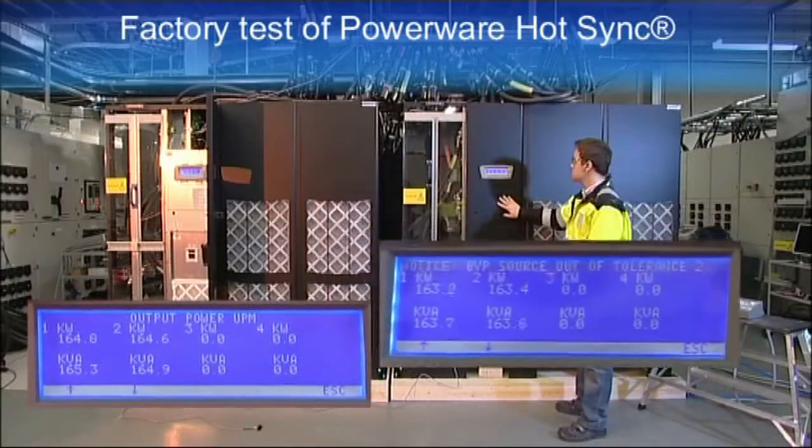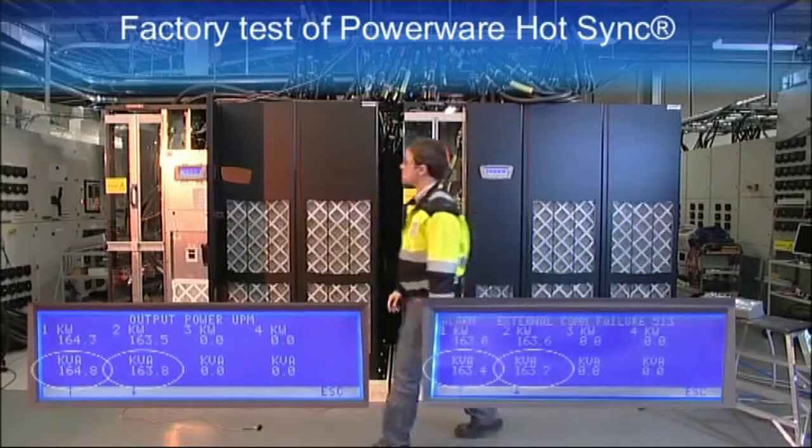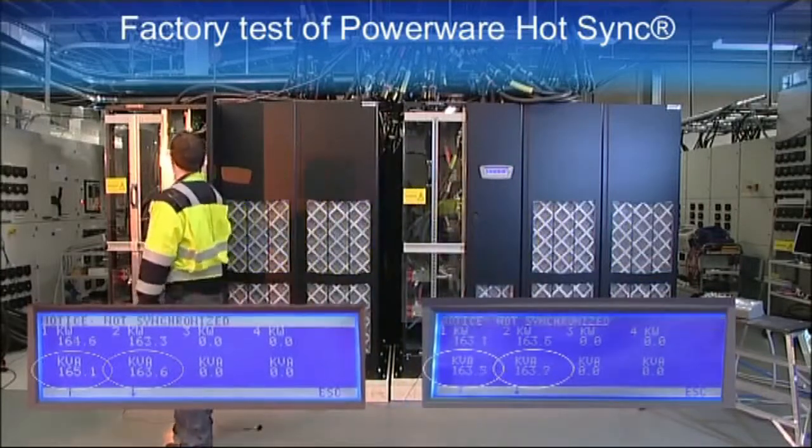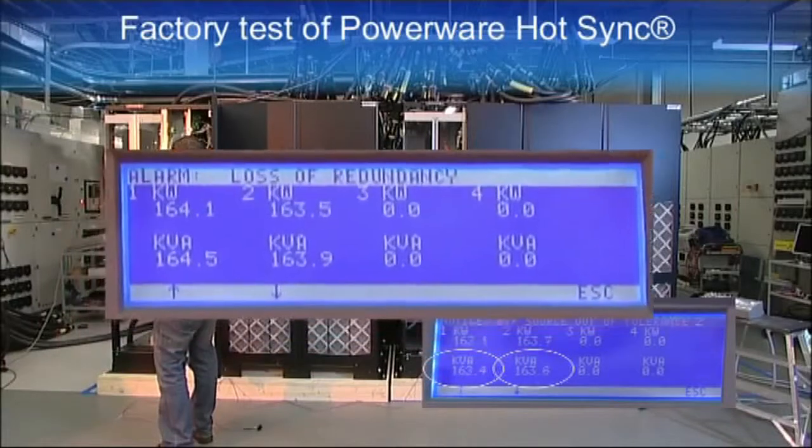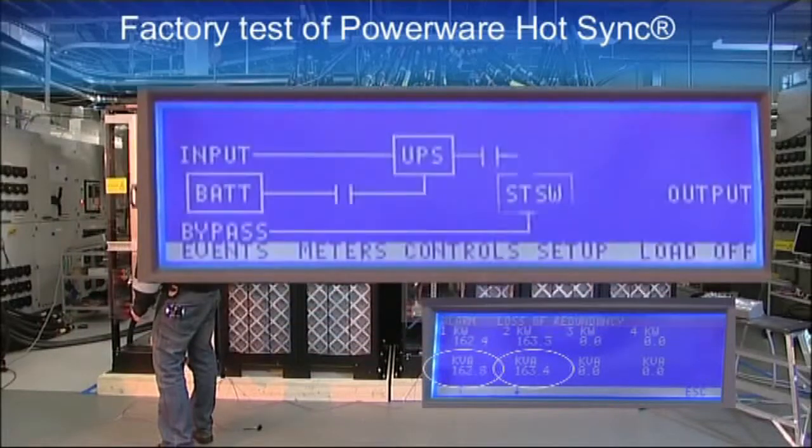When the load level rises, the inverters are monitoring output power independently and can, with this information, share the changing load level even without communication.